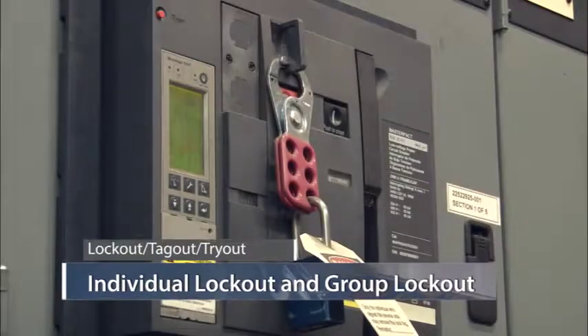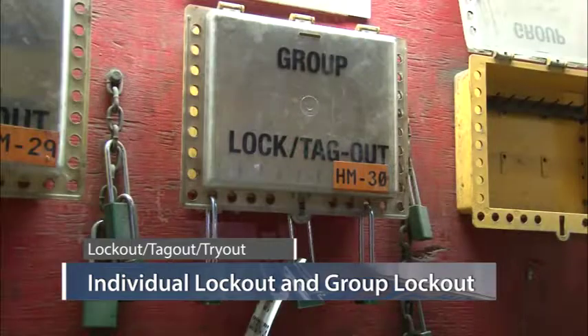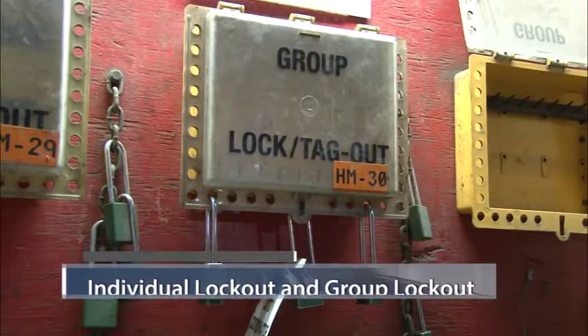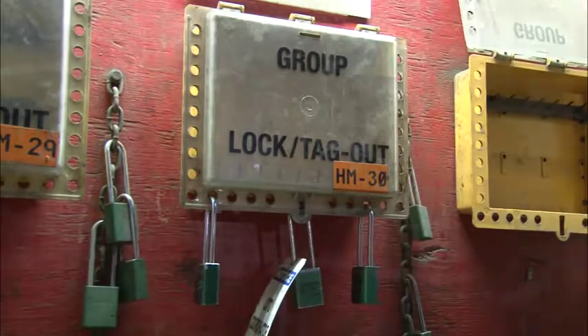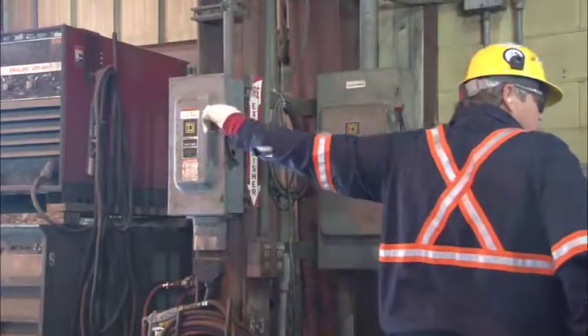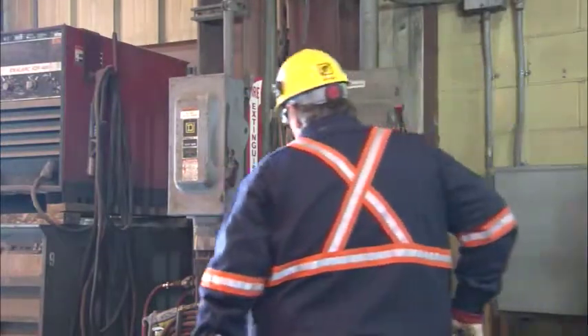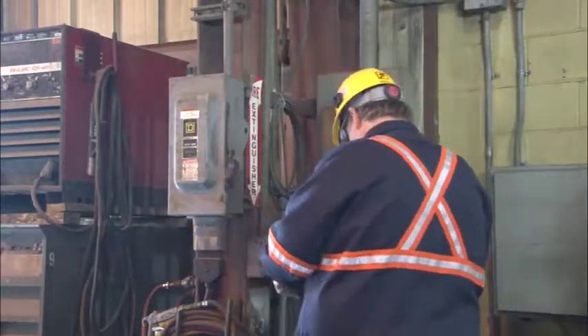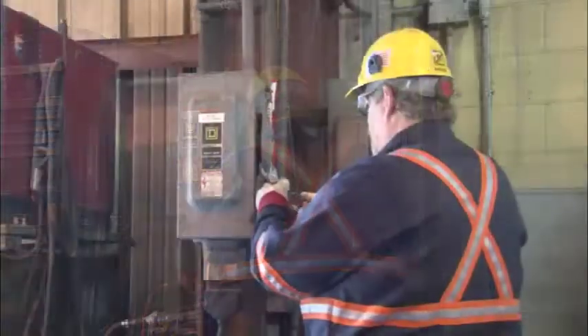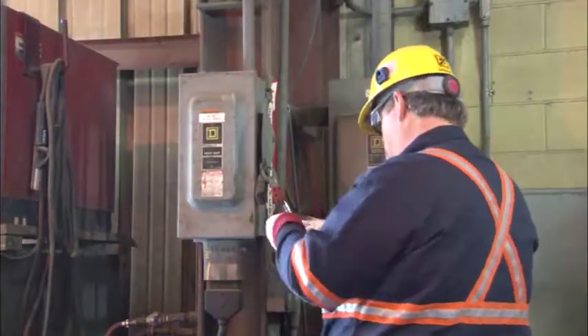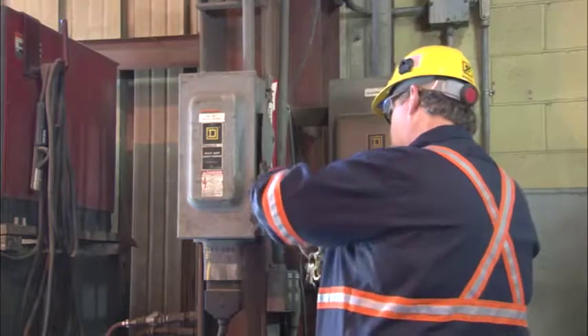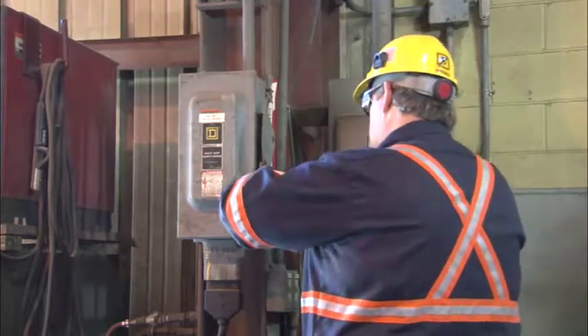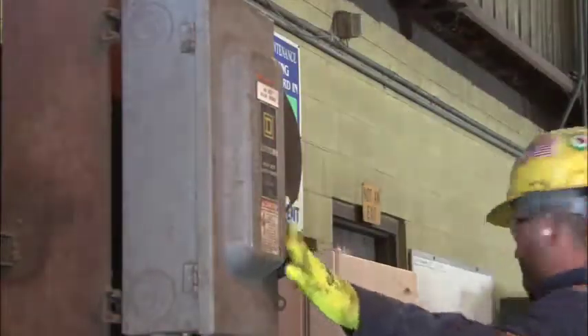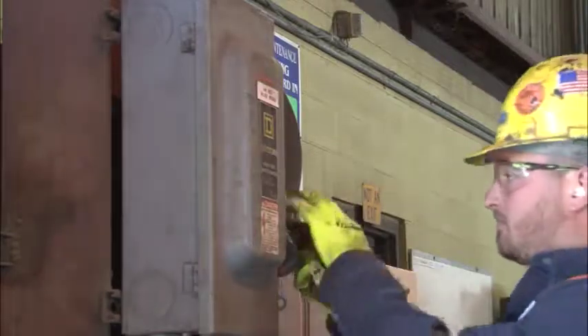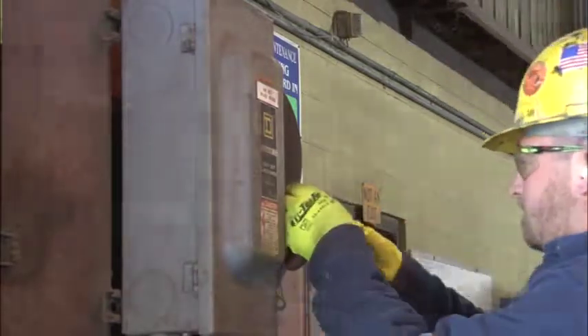Now that we know the steps involved in executing proper lockout, tagout, tryout, we will now discuss the difference between an individual lockout and a group lockout. An individual lockout is performed when only one authorized employee is performing the servicing or maintenance. In this situation, the individual working on the equipment will place the one energy isolating device in the safe or off position and simply apply their personal lockout lock to the energy isolating device.